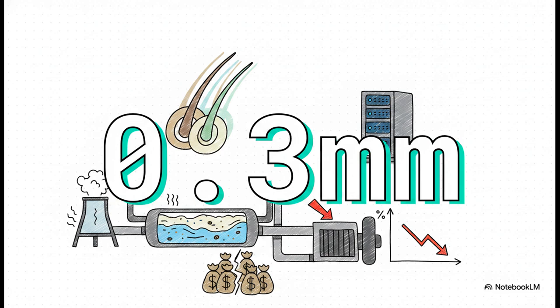In a water-cooled condenser, outside water is constantly carrying minerals and dirt through the tubes. If just 0.3 millimeters of scale builds up, it acts exactly like a clogged artery. The condenser can't shed heat properly, the compressor has to work overtime, and energy efficiency drops by up to 15%. In a giant AI facility, that tiny layer of dirt literally wastes millions of dollars in electricity.